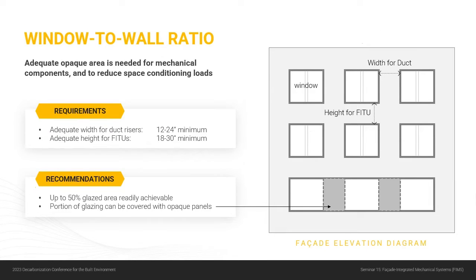Now, another really important aspect of the facade is the window-to-wall ratio, because if we're running all this mechanical on the outside of the building, we need opaque area to actually run it. So if you have a fully glazed facade, that's going to be a problem. You need adequate width between the windows to run your risers, and adequate height below the windows to actually place your fit-U. So there are some constraints on the maximum glazed area, but you can definitely comfortably get up to 50% glazed area, potentially even more than that.